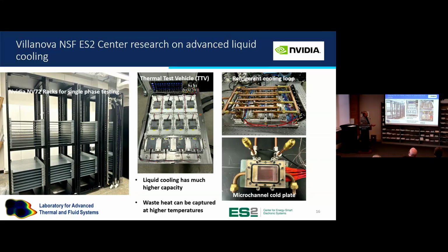This entire system is designed to let you cool one of these by placing what's called a cold plate on top of the GPU, then circulating fluid through the channels in that plate, picking up the heat and removing it from the server. These hoses — although this is a single-phase system, a two-phase system would be similar — are gigantic hoses bringing fluid into the cabinet and taking fluid back out. At the heart, at the lowest scale, is this cold plate, designed to absorb the heat from one single CPU.